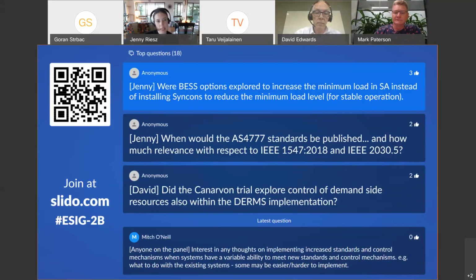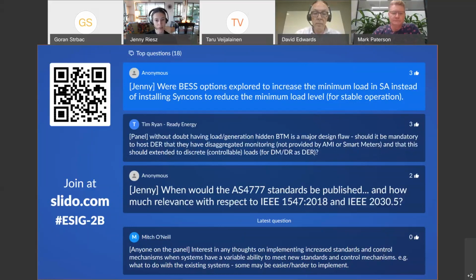The synchronous condensers being installed in South Australia are not related to minimum load. They're being installed to provide system strength and inertia, which are completely separate requirements. So it's incidental that they also assist with minimum load levels.